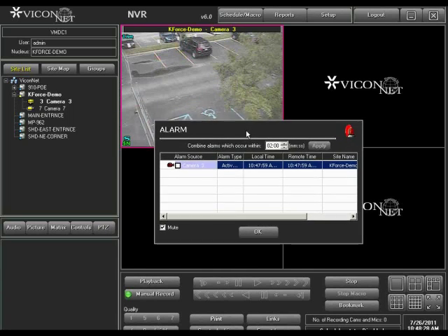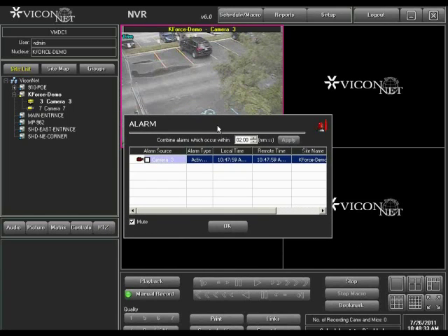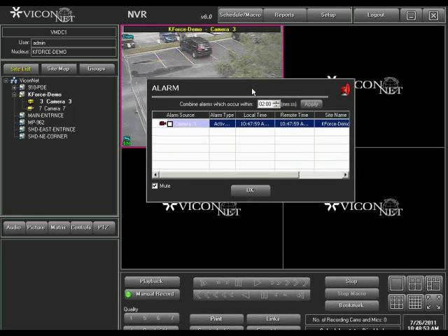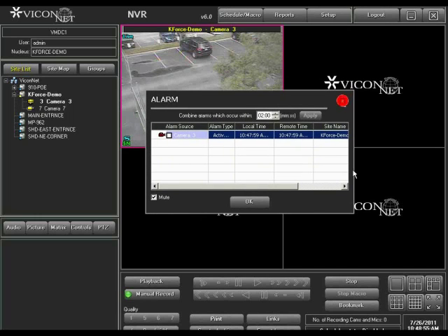Is that understood? Yep. Okay, because if a minute had not passed between the previous alarm, then the alarm is not generated. If the alarm is not generated, it does not trigger the macro on the collector. It will not send the alarm, and I will not receive the alarm. And ever since I did that, enough time had passed, and then I received the alarm.